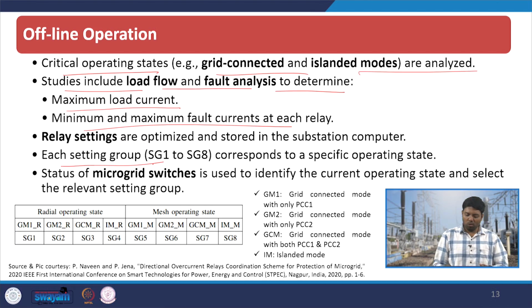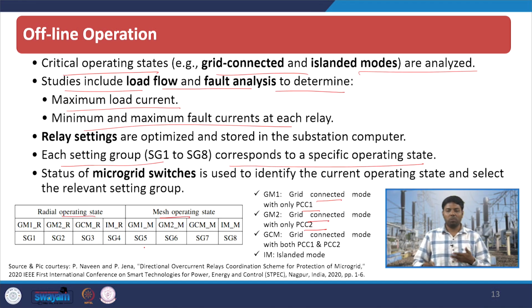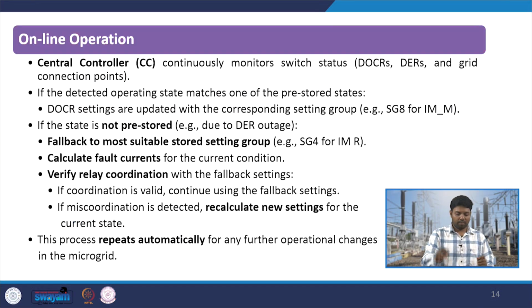So, each setting group corresponds to a specific operating state. You keep different PCC connections, you keep the radial or the mesh network, and depending upon that you determine the pickup and the TDS value settings.